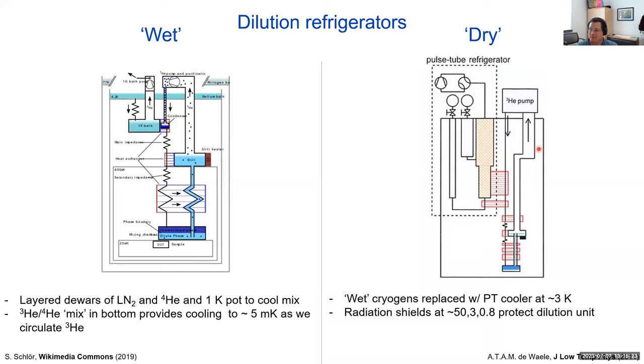The second question was, can you mix wet and dry fridges? Yes — you can get a dry fridge with a liquid nitrogen pre-cool circuit; that is an option you can commercially buy. You wouldn't usually mix helium-4 and the pulse tube, because it's kind of like having a hat on top of a hat. But liquid nitrogen pre-cool circuits and similar things exist that you can buy for these fridges, making a mixed wet-dry fridge.